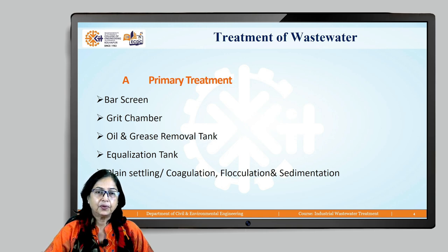Now here, only the wastewater which comes from the mill house contains oil and grease, so it is separated and first treated for removal of oil and grease, and after that it is allowed to mix with the wastewater from other processes. So, wastewater from the boil house is mixed with wastewater from the mill house only after removal of oil and grease from the mill house effluent.